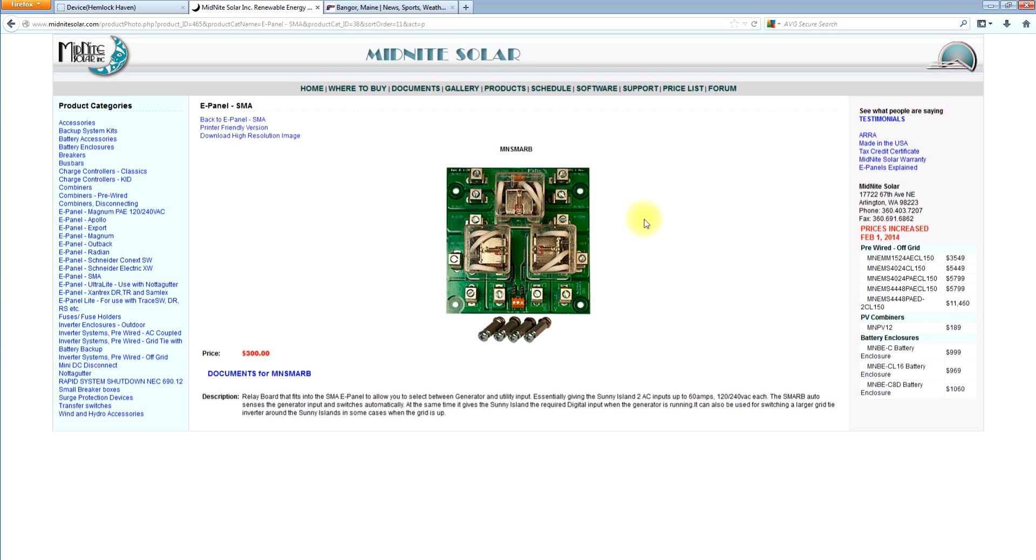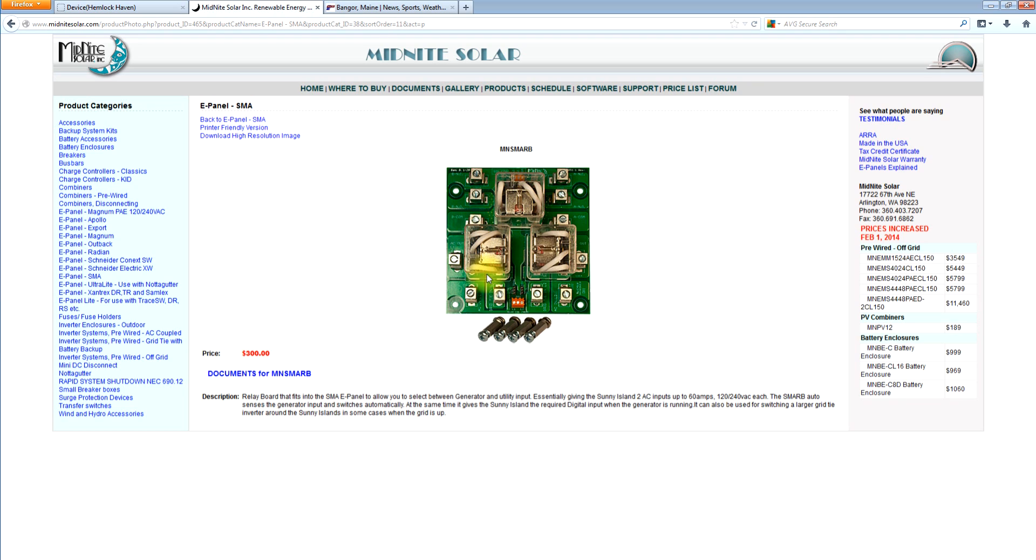And we also use this same board inside our AC coupled with some delay relays and stuff to do the larger grid tie inverters. Because basically with the SMA, the issue you really have is that it has a 56 amp internal relay, and that's at 120 volts. So if you try to put 12 kW of Sunny Boy on a single Sunny Island, what would happen is when the relays closed, it would try to pass too much current and the inverter would shut down on over current. So what we do in that case is we wire this into some delay relays. And we actually transfer the Sunny Boy straight over to the grid when the grid is there and bypass the Sunny Island to get around that 120 volt 56 amp relay.